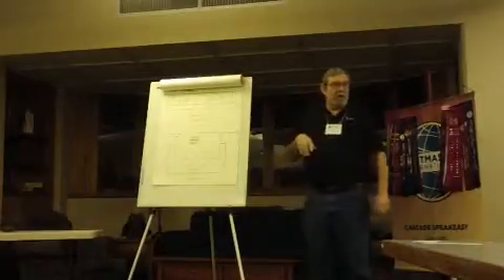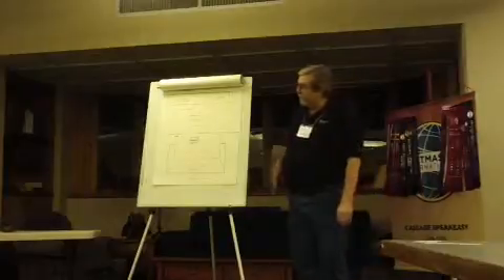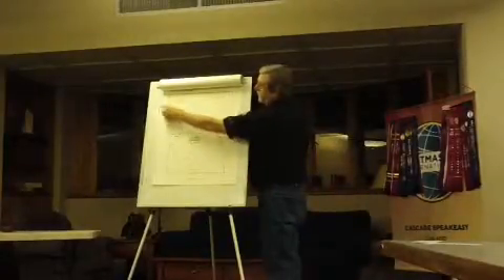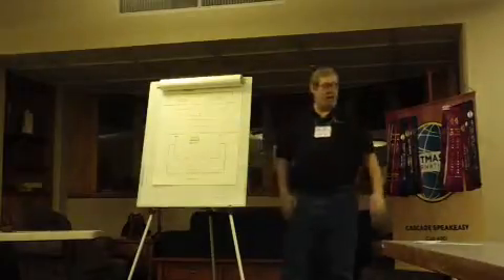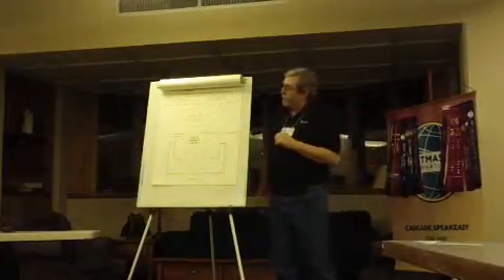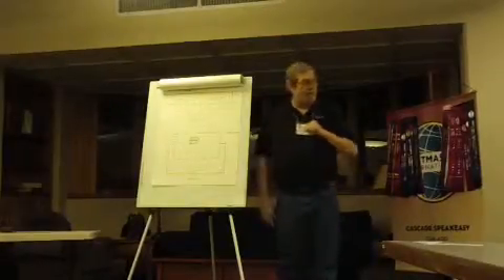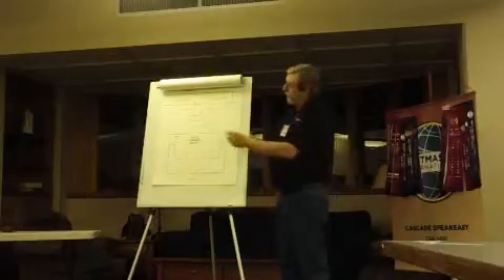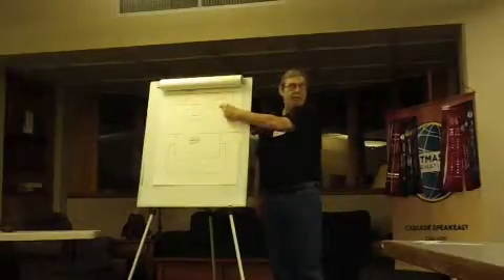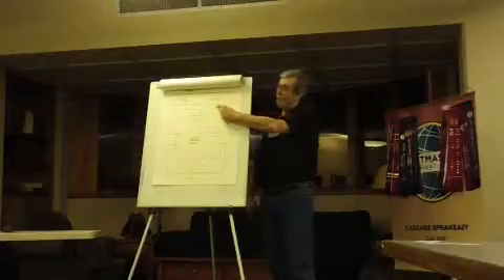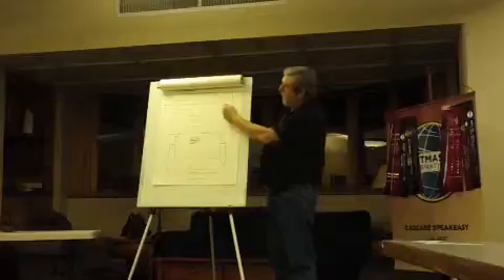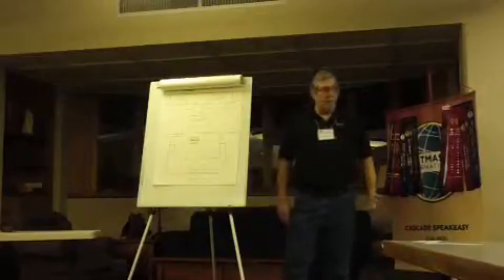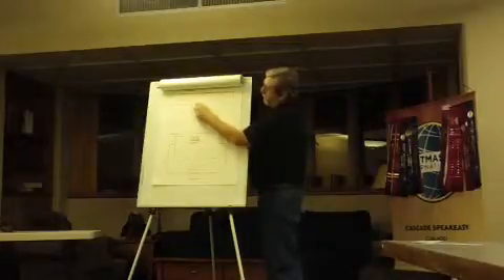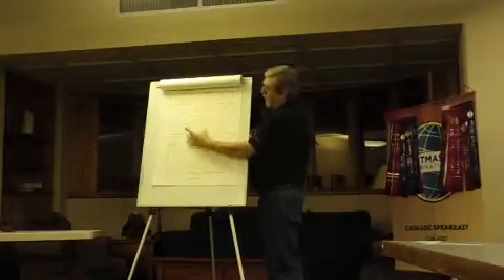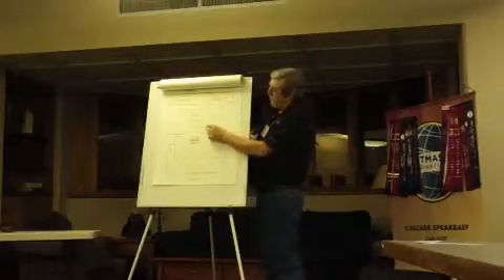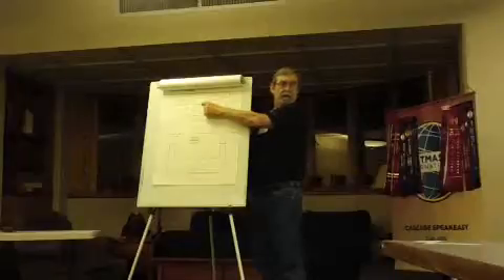So since we have alternating current coming from our generator or utility company, the first thing that I'm going to do whenever that power runs right into this UPS system is I'm going to run it into a rectifier, and that's part of this UPS system. So this rectifier, the thing that it does is it's going to transfer the alternating current to direct current. Then as the power flows right on through, I'm going to run it next to an inverter. And that inverter is going to convert the direct current back to AC current, and it's going to go back out and downstream to feed my computers. So at the point that I have transferred that to DC right here, direct current, I'm going to tie a bunch of batteries. And at my site, I have 120 batteries that connect right here inside this UPS.